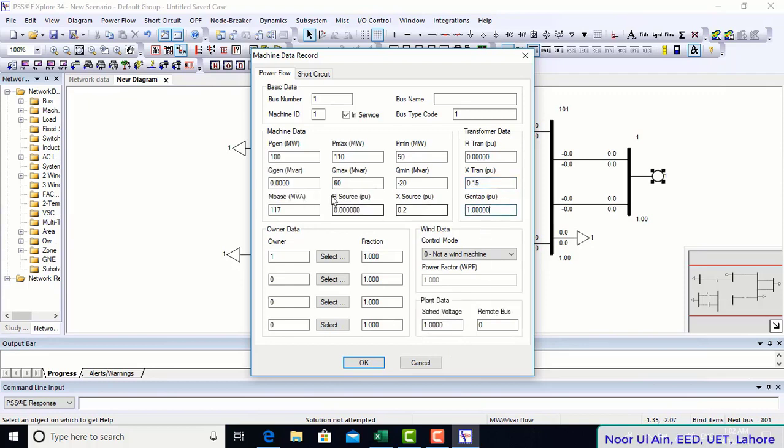see its impact. So for a generator section, you have to specify the Pgen and Pmax, Pmin. This is 110%, this is 50%. Qgen is never specified. Qmax and Qmin are specified. If not given to you, you can compute it based upon the given power factor. You can compute the apparent power by the given power factor and the rated real power.